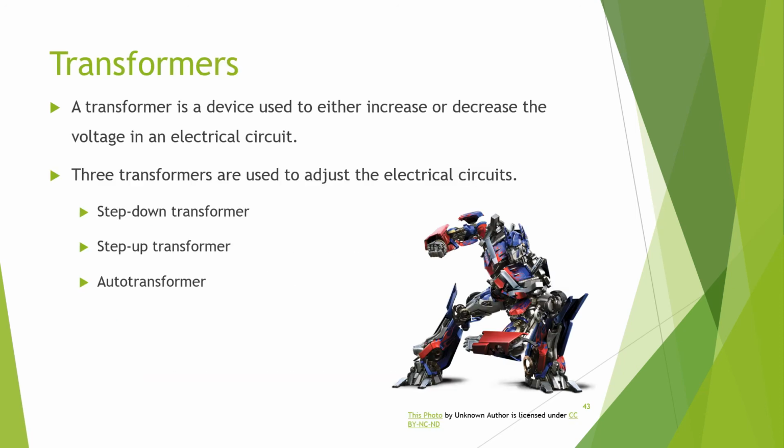The transformers that are inside the tube head are used to transform, essentially, the electrical current. We have the step-down transformer, the step-up transformer, and the autotransformer. They do what they sound like they do. So the step-down transformer takes that incoming 110 to 220 line voltage, and it pulls it down to that 3 to 5 volts that we need in the low voltage circuit.